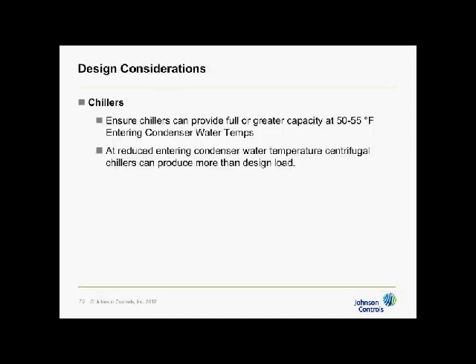To achieve this, of course, you have to look at some design considerations. One of the most important on the chillers: you need to make sure that the chillers can provide full or greater capacity at low entering condenser water temperatures, down to 50 to 55 degrees Fahrenheit. Also, at reduced entering condenser water temperatures, keep in mind that centrifugal chillers can often produce more than design load.